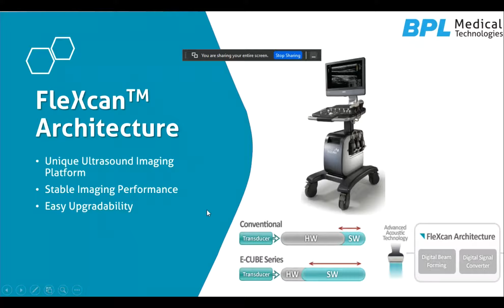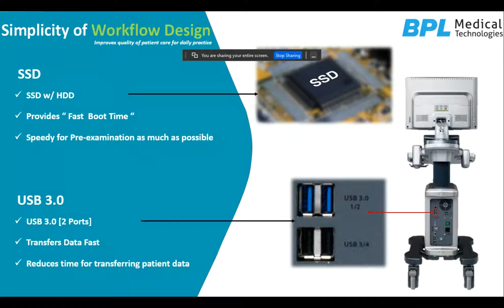And this machine is based on a FleXcan architecture. The main advantage of this architecture is that whatever images you are getting today will be there years after as well. So it ensures stable image performance throughout the ultrasound's life. That's the strength of this platform. And this machine is based on an SSD, solid state drive. As a result, you get a fast boot up time, and like your laptop, you can do multiple functions. When you are transferring data, you can also scan the patient at the same time, because the machine's processing power is really good.